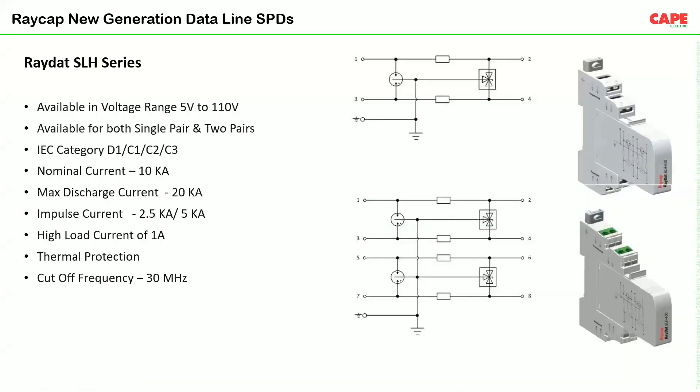The Raydat SLH series SPD is tested as per IEC categories D1, C1, C2, and C3. It has a nominal discharge current of 10 kA and maximum discharge current of 20 kA. The impulse current rating is 2.5 kA per pair — for a single pair 2.5 kA, for two pair 5 kA. Load current is around 1 ampere, which is quite high for communication — generally communication load current is in milliamps. It has integrated thermal protection and a high cutoff frequency of 30 MHz. Frequency is a very important parameter when selecting a data SPD — the SPD must cover the frequency range of the target communication system.